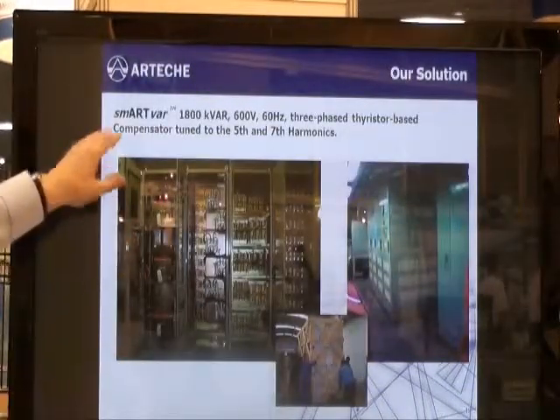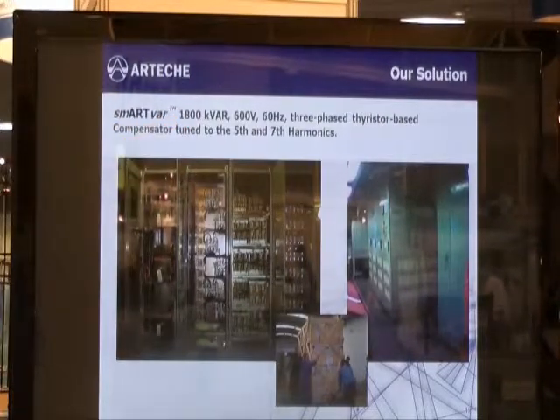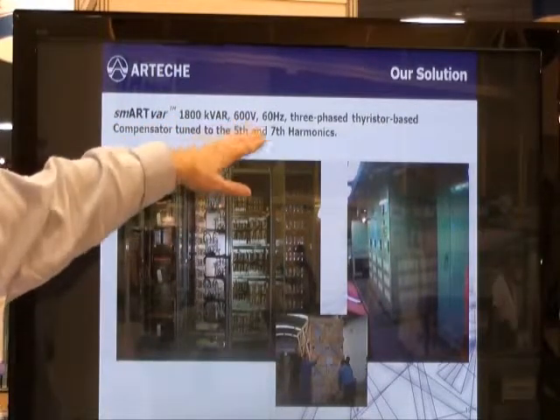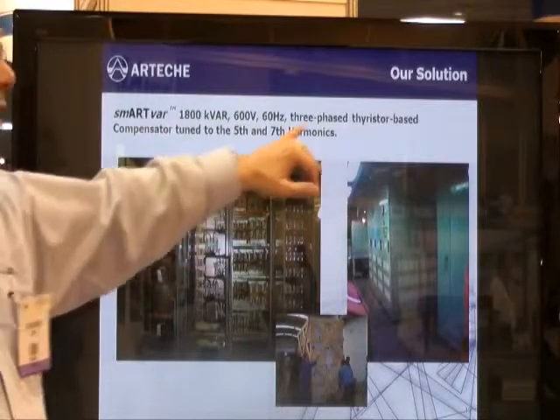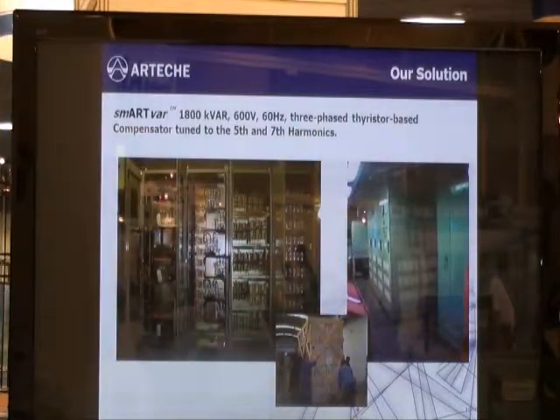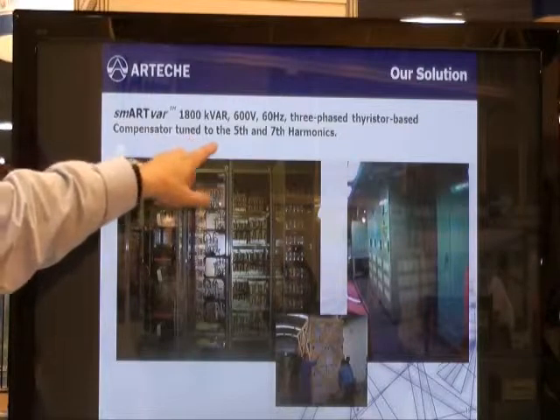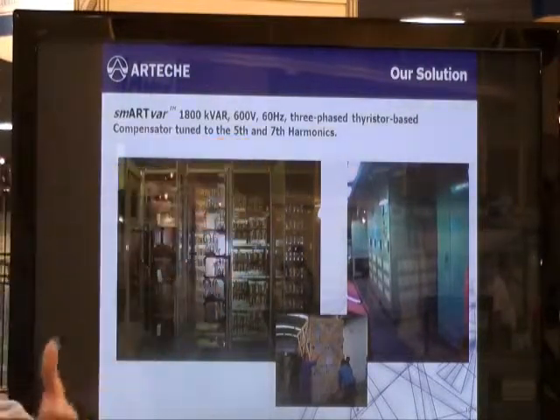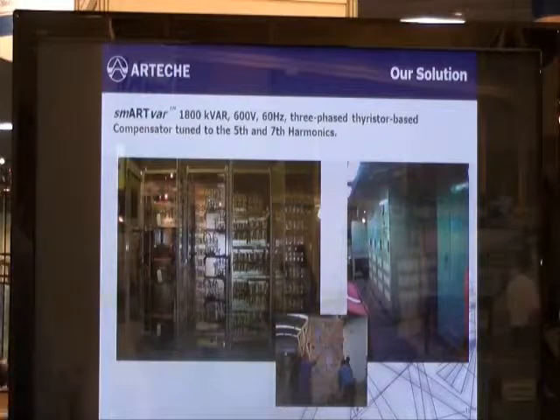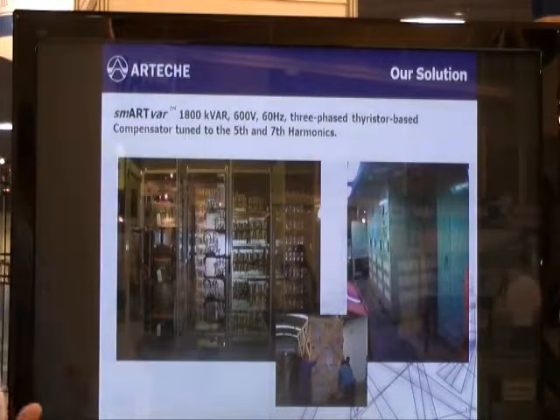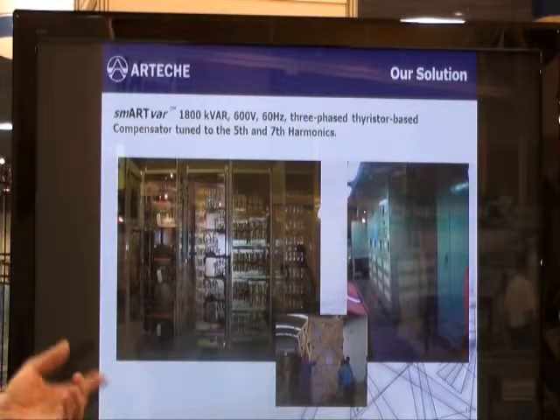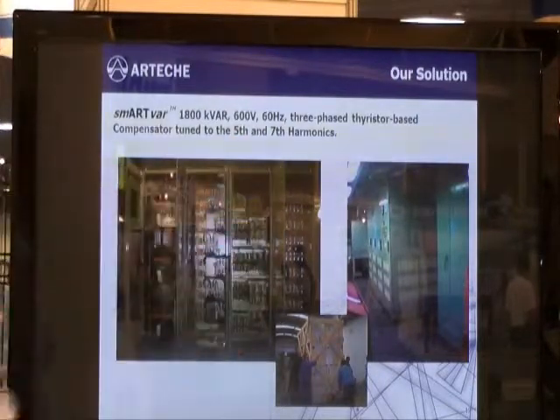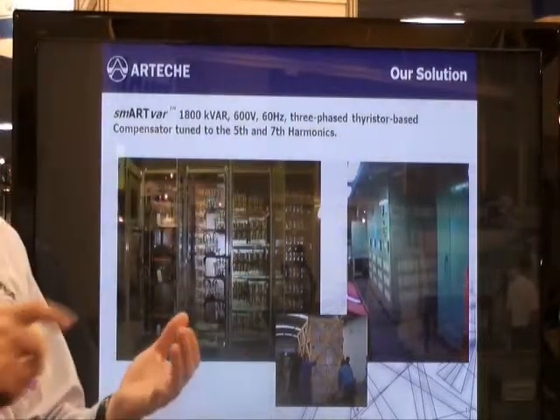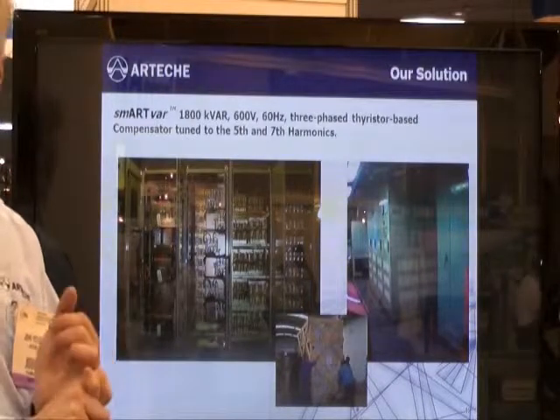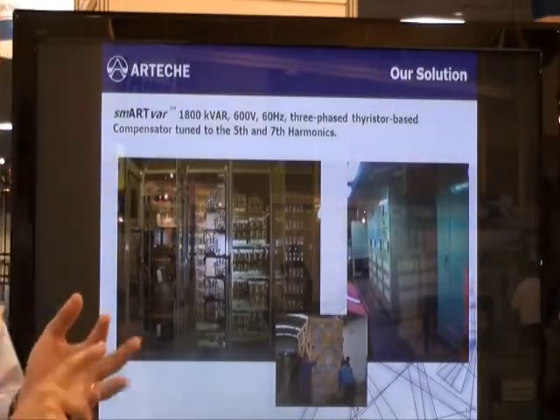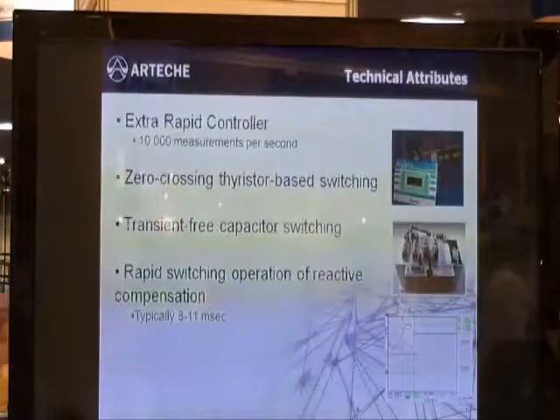So our solution was an 1800 kVAR SmARTvar, 600 volt class, 60Hz. This is a thyristor switch with the new SmARTvar switch, and we compensated the system with both a 5th and 7th harmonic filter, because the customer's objective was to not only achieve the high power factor but also to reduce harmonics. The 2 most significant harmonics in this case were 5th and 7th, so we designed this to provide the kVARs for power factor improvement, as well as harmonic filtering.